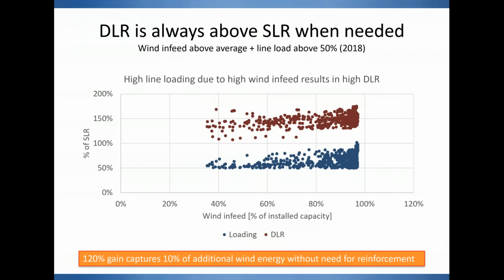And what do we see on this plot here? You see that naturally when the wind blows, the wind farms generate, so the wind in-feed increases. These are the blue spots here on this graph. And at the same time, when the wind blows and generates more wind in-feed, you also have, and that's the vertical axis on this chart, increased capacity of that particular line. This is represented here by the purple dots. So you can see that the extra capacity delivered by DLR allows to accommodate this additional wind in-feed that is produced by offshore wind farms.